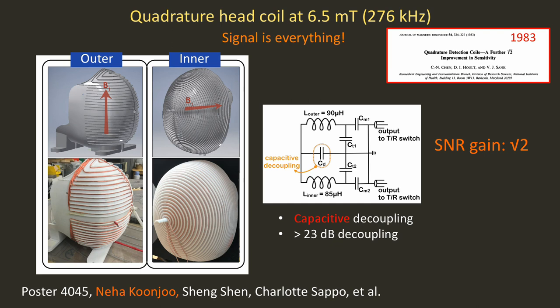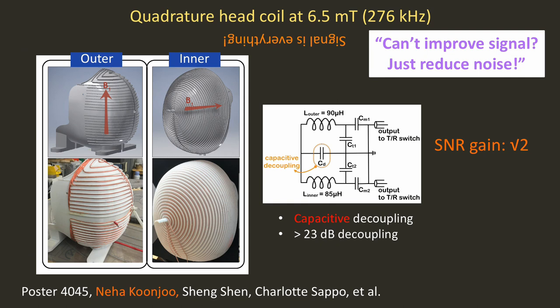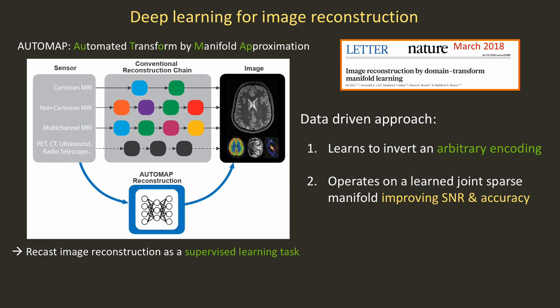We continue to evolve our hardware. This is a quadrature coil that Neha Koonjoo built, taking a page from David Hoult's work, giving us a factor of root-2 in SNR — a factor of 2 in acquisition time. But at some point our sequences are maximally efficient, we're at the Johnson noise limit, and we have no other place to go. The joke in my lab is: we can't improve the signal — can we just reduce the noise? About two years ago, my postdoc Boju took this very seriously when he wrote down his pioneering deep learning image reconstruction approach called AUTO-MAP: automated transform by manifold approximation.